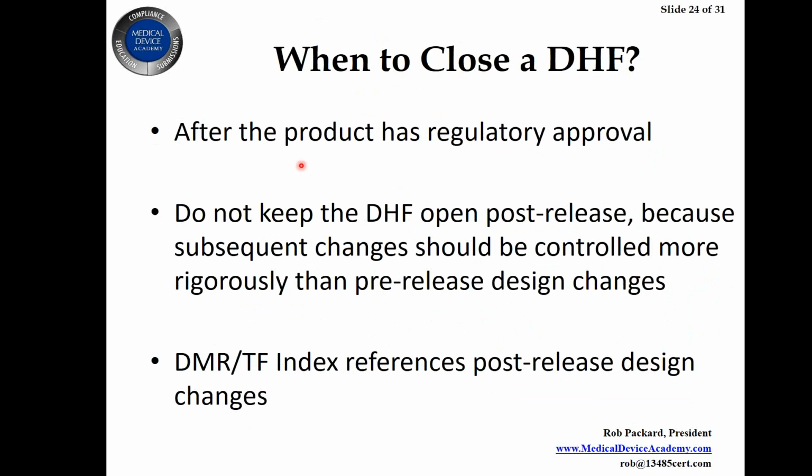When should you close your DHF? After the product has regulatory approval is the best practice. The reason why is that way, when the FDA comes in and they want to know about design changes, you can say, well, this was the original 510K and we made these changes afterwards, and here's the verification and validation we did, and here's our letter to file indicating why we didn't have to do a new regulatory submission. So you want to keep it separate. Here's what was approved and here's the post changes.